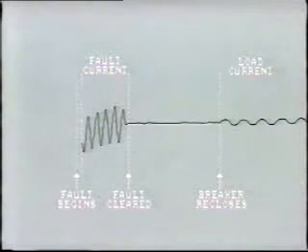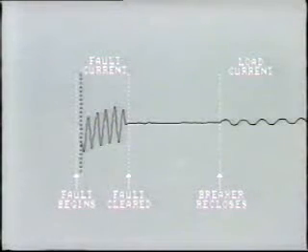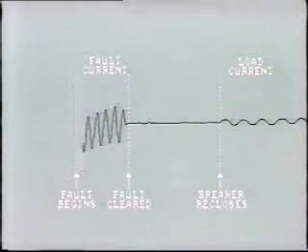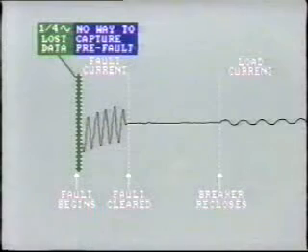The quick start oscillograph is the simplest type and uses a high-speed recorder. As soon as a fault is sensed by a protective relay or other sensor, the machine starts and the paper begins to move after three or four milliseconds. This presents a problem since the data at the very beginning of the fault is lost — about one quarter cycle. Also, there is no way of capturing conditions just prior to the fault. In spite of these disadvantages, many users prefer the quick start system, willing to accept some data loss in exchange for the simplicity of the machines.